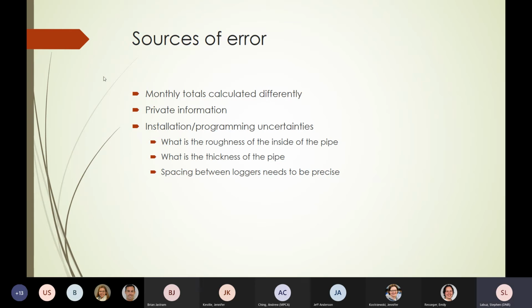Another source of error, which could involve 1, 2, or 3 percent error, is installing and programming uncertainties. When you install these transducers, they hook into a logger, and you have to program the logger before reading valid numbers. The logger asks for things like roughness and thickness of the pipe, and those are mostly uncertain. We read tables, look up specs, and sometimes call the irrigator themselves to ask for their opinion on the outside diameter of the pipe. They might say it's typically an eighth inch thick, but we know the outside diameter is slightly higher, so we adjust our numbers.